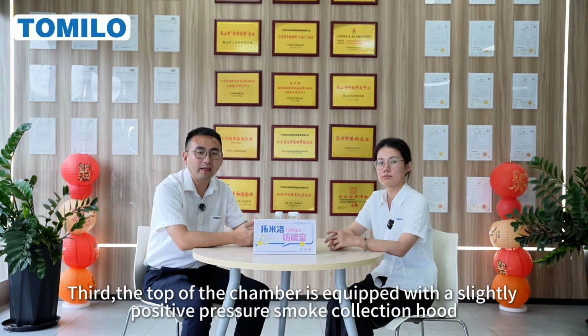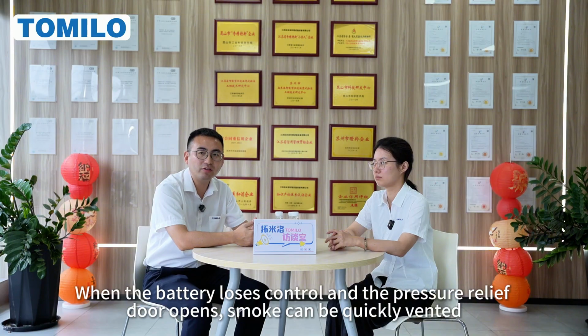Third, the top of the chamber is equipped with a slightly positive pressure smoke collection hood. When the battery loses control and the pressure relief door opens, smoke can be quickly vented.